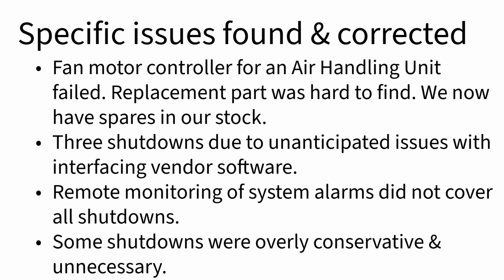We discovered that the replacement part was surprisingly hard to find, and it took us almost 5 days searching the country to find that part and get it here. So we looked at the whole system and found there are only 2 or 3 of these type controllers that were a single point of failure. We have many of them, but they usually have 2 pumps or 2 controllers so there's always redundancy. But for the air handling units, there's only 1. So we ordered and now have in stock spares for the couple in the air handling units. If this ever occurs again, it shouldn't take us as long.